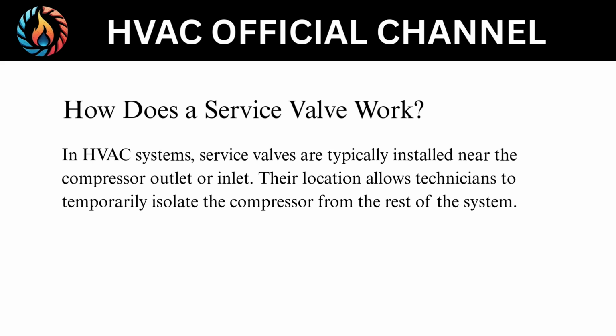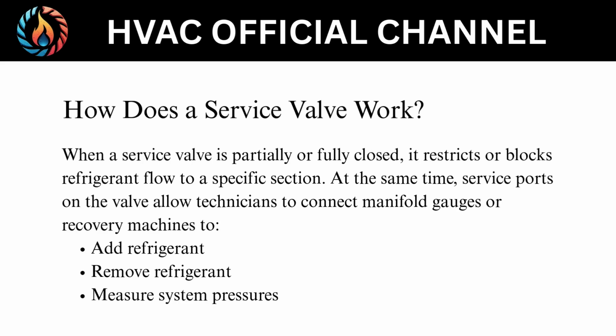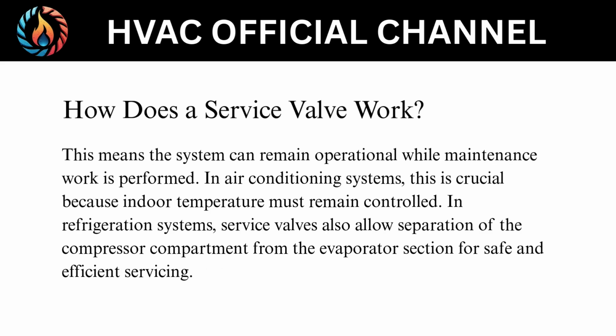How does a service valve work? In HVAC systems, service valves are typically installed near the compressor outlet or inlet. Their location allows technicians to temporarily isolate the compressor from the rest of the system. When a service valve is partially or fully closed, it restricts or blocks refrigerant flow to a specific section. At the same time, service ports on the valve allow technicians to connect manifold gauges or recovery machines to add refrigerant, remove refrigerant, measure system pressures. This means the system can remain operational while maintenance work is performed.